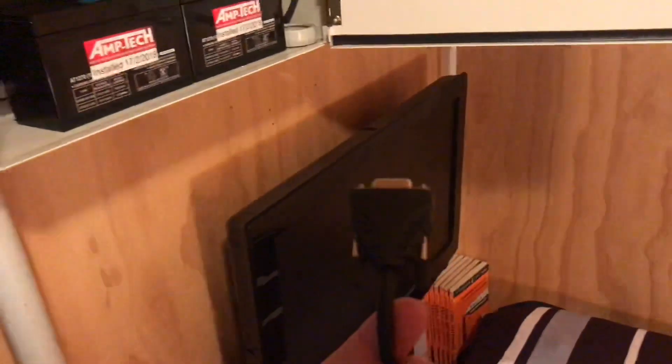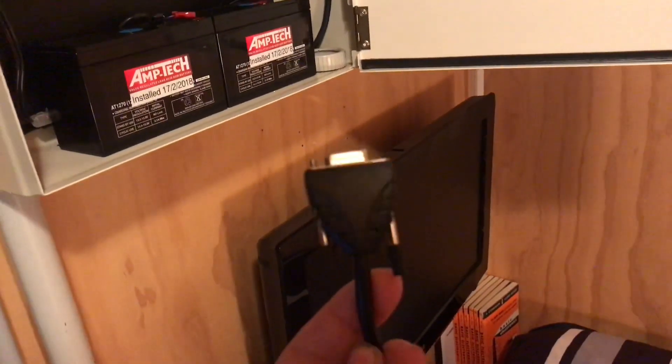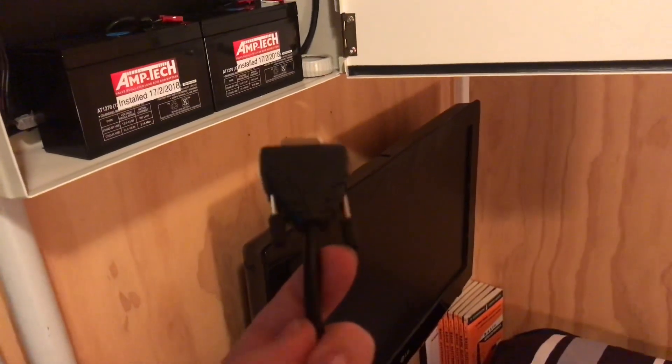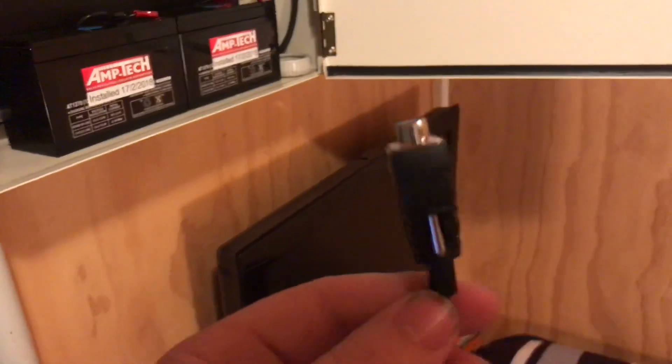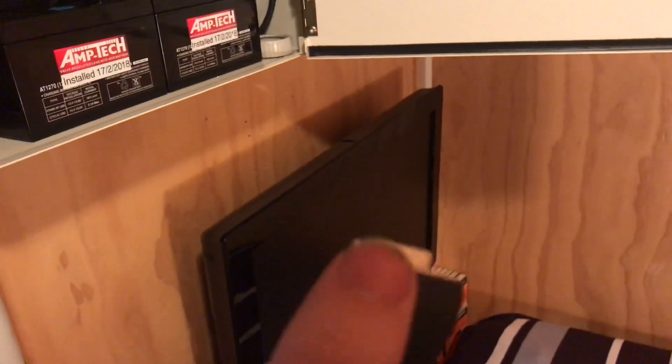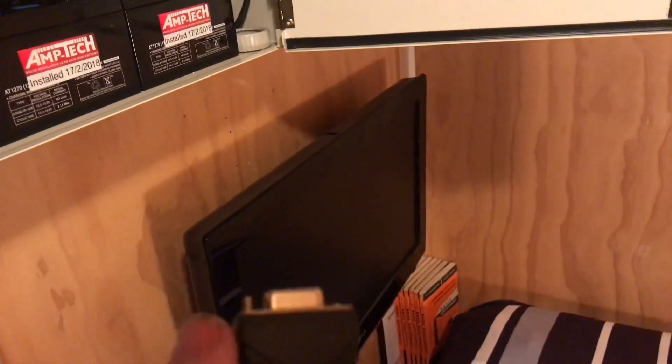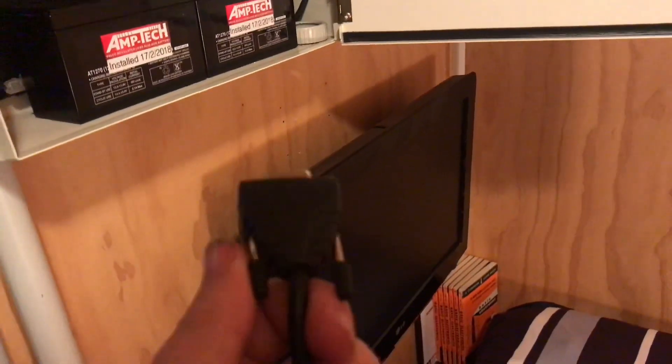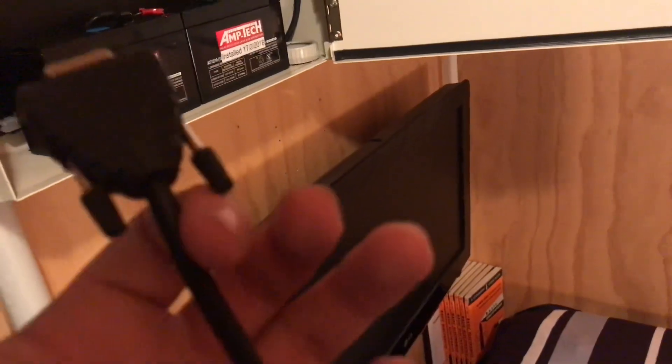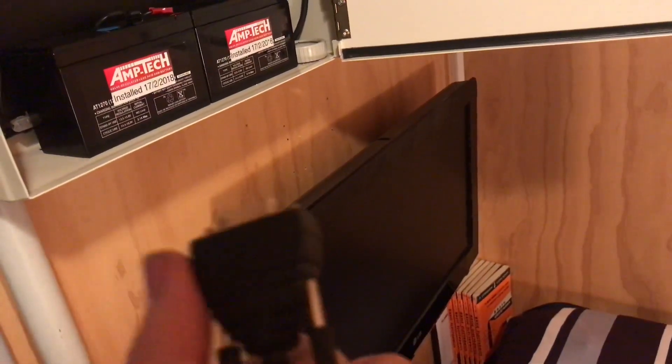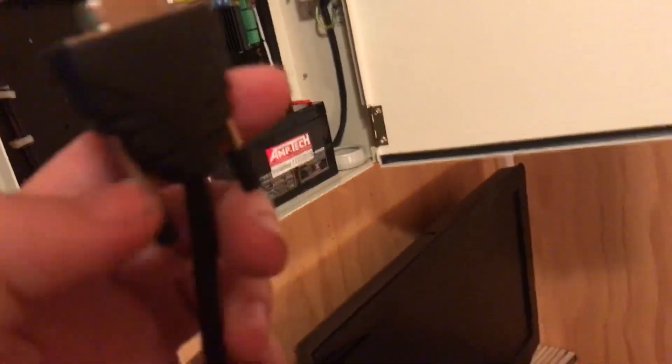To start off with, we need to connect the panel to the computer, so we'll need a cable to do that. Something to keep in mind with the Petronix panel is you will need a null modem cable. What this is in a nutshell is a crossover cable essentially. So it swaps the data pins around. There's different kinds of null modem cables, but this is just a basic switching null modem cable. If you don't have one of these, you're not going to have any luck connecting to the panel.